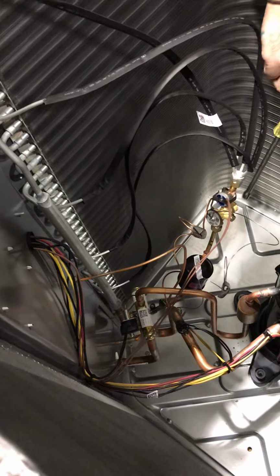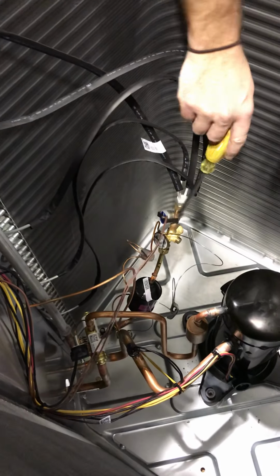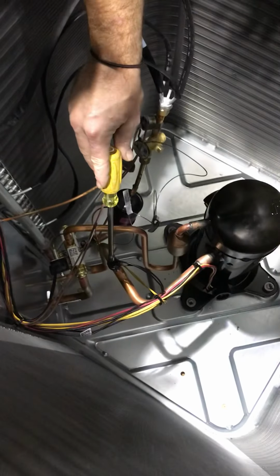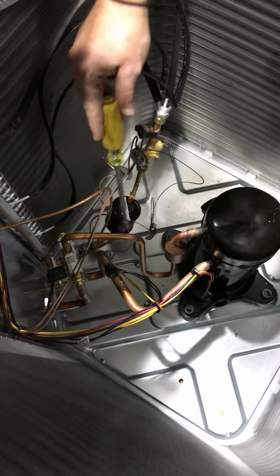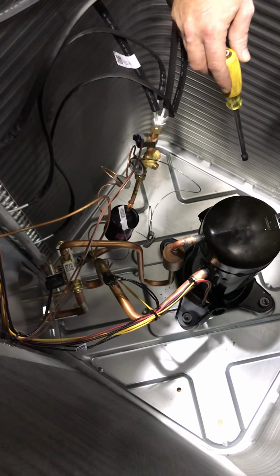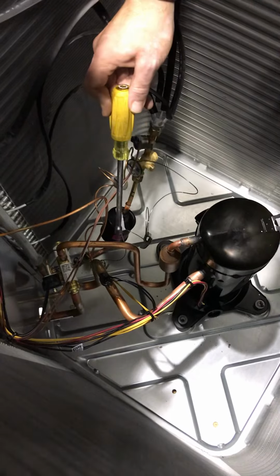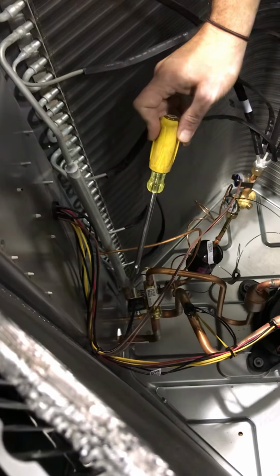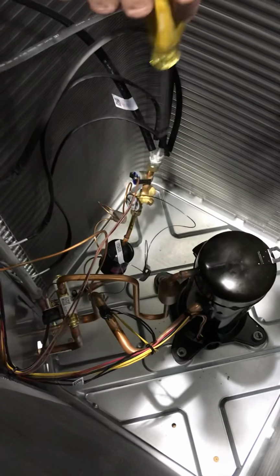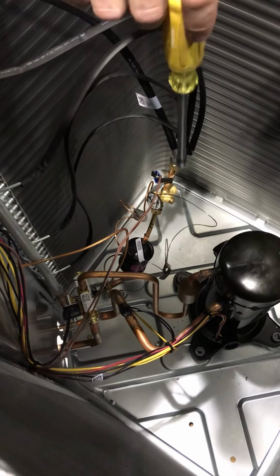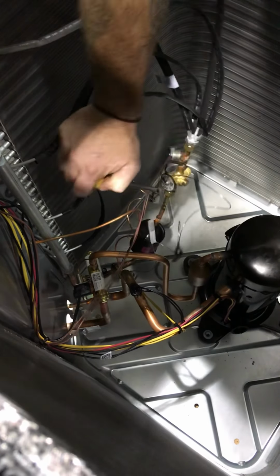All right. Pretty much a simple design. You've got a coil sensor and a low pressure transducer, which regulates your pressure. So if my pressure is too low, it's going to send a signal, or if it's too high, it's going to send a signal, and it's either going to send it into defrost mode, or it's just not going to turn on. And then I have the same thing down here, my high pressure transducer, which is way down here on my high pressure line. Okay.